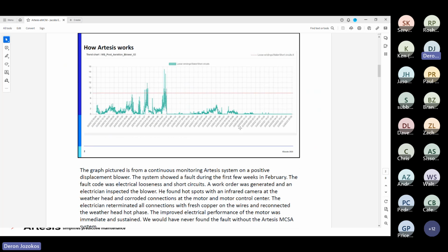What he saw here, he was alerted automatically by the system of a fault, and the fault code was electrical looseness and short circuits. So he generated a work order for the electrician to inspect the whole system. Using an infrared camera, he found hot spots at the weatherhead and also corroded connections at the MCC bucket. The electrician re-terminated all the connections with fresh copper on the wires and reconnected the weatherhead hot phase. The improved performance of the motor was immediate and sustained, and he credits the Artesis system for having found that.